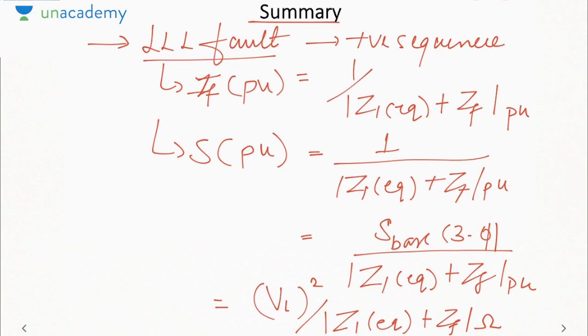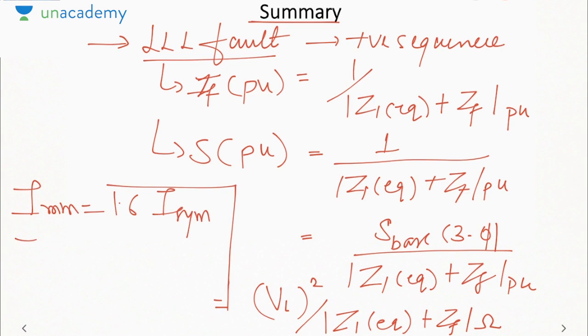Okay. Then we saw the momentary current of a circuit breaker, which is 1.6 times I symmetrical, and we saw the breaking current, that was K into I symmetrical, where K depends on speed of circuit breaker. It is 1.1 for 5 cycle circuit breaker, 1.2 for 3 cycle, and 1.4 for 2 cycle circuit breaker. Okay, so this is what we covered in this lecture. Rest of the symmetrical fault analysis we will see in the next lecture.